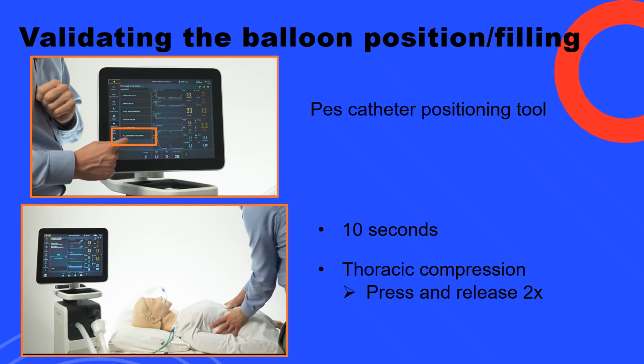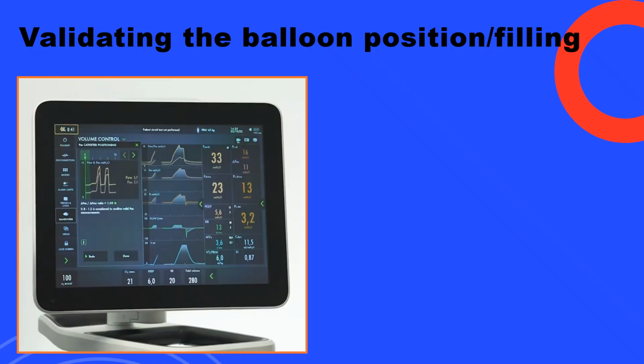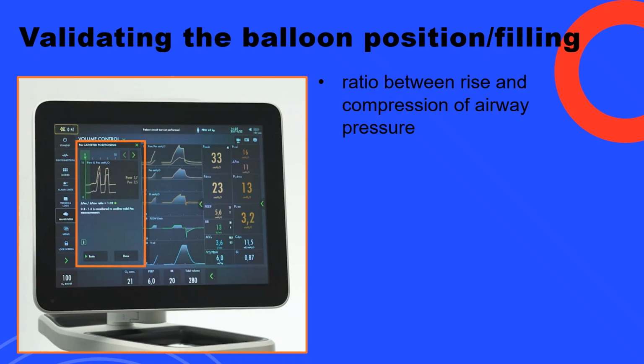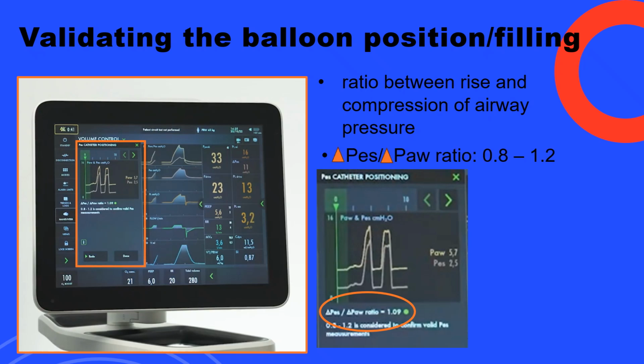The ventilator calculates a ratio between the rise and the compression of airway pressure. After the maneuver has been performed, the Servo-U will calculate the ratio between the rise and compression of airway pressure. This reflects the difference or the ratio between the changes in esophageal pressure and airway pressure. The pressure ratio should be between 0.8 to 1.2. And for this maneuver, a calculated ratio is 1.09, which is acceptable. And this validates the correct position and filling of the esophageal balloon catheter. This is important in calculating the transpulmonary measurement, since Servo-U automatically calculates it.